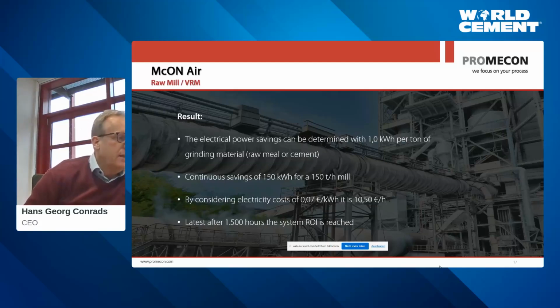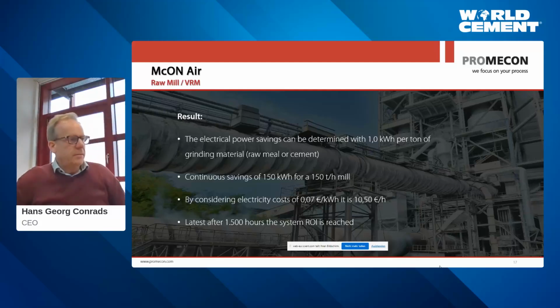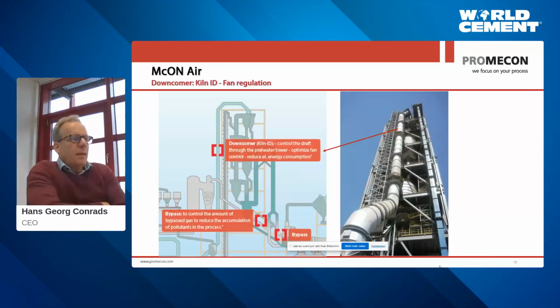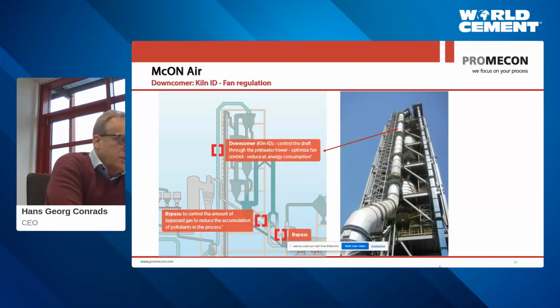The savings that you're usually looking at with typical mill size would be 1 kilowatt hour per ton of grinding material. So we're talking here about 1,000 hours, 2,000 hours of return on investment for a mill. Not much. So a very small measurement that is accurate will give you a big saving on the mill. The next application I would like to discuss with you is downcomer. Downcomer is our most popular application. We have many, many systems out there that are measuring downcomer.